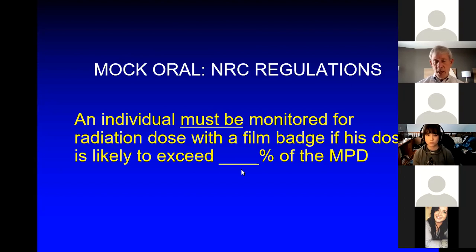Anybody asks you about a percent, the answer is always going to be 10%, always, with the sole exception of prescribed doses and administered doses. Everything else is 10%. There are 4 dose calibrator tests. What's the limit? 10% for all of them. So if you don't know, go for 10%.